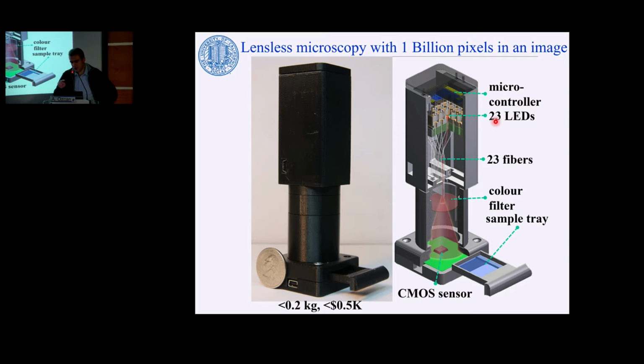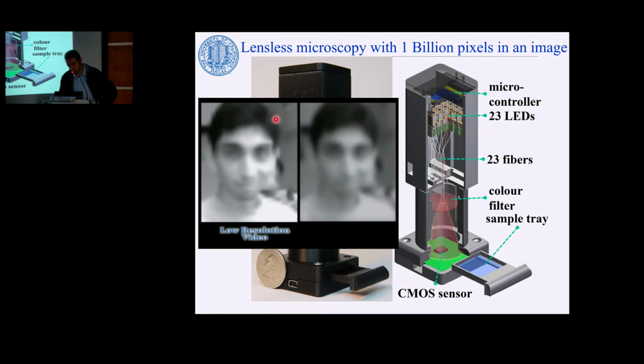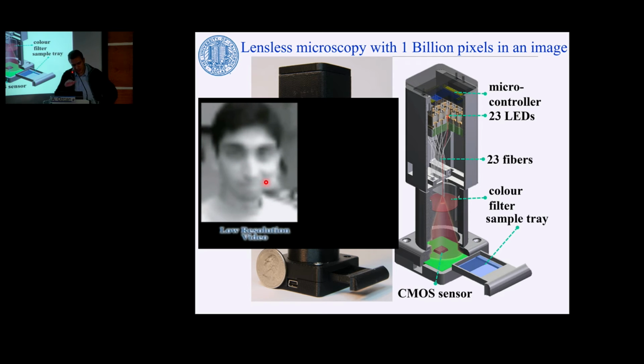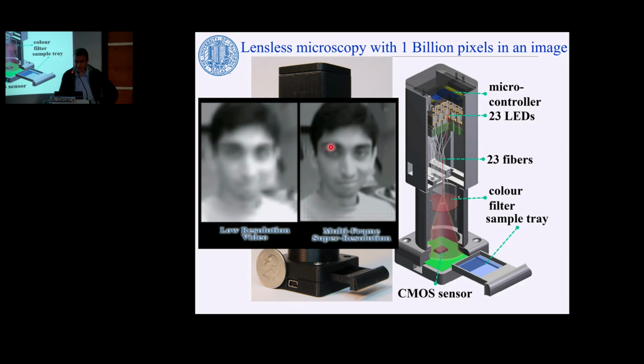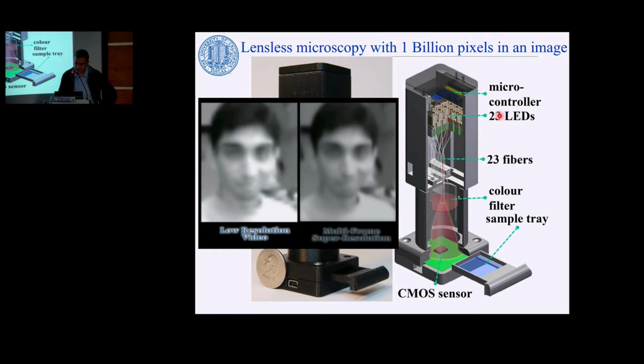There is some additional illumination unit here, some LEDs. Basically, they turn on and off to create subpixel level shifts. The framework behind this kind of microscope is pixel super resolution, which means rather than looking at a single frame that is low resolution, we look at a few, maybe 5 to 10 frames, where they're slightly shifting with respect to each other, and we synthesize a super resolved image. This is macro scale. We do this at the micro scale, but there's nothing mechanically moving in these designs because we turn the LEDs on and off digitally.